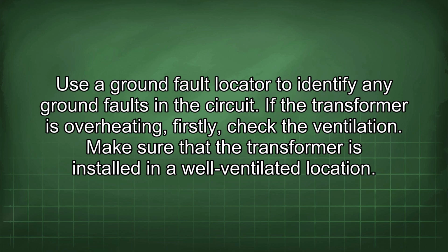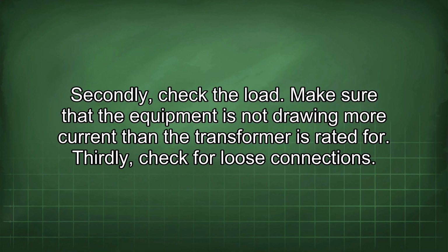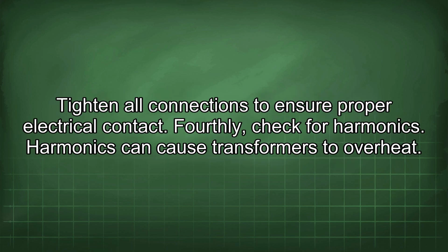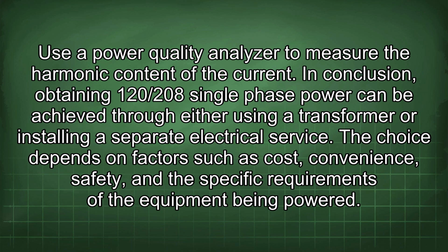If the transformer is overheating, firstly, check the ventilation. Make sure that the transformer is installed in a well-ventilated location. Secondly, check the load. Make sure that the equipment is not drawing more current than the transformer is rated for. Thirdly, check for loose connections. Tighten all connections to ensure proper electrical contact. Fourthly, check for harmonics. Harmonics can cause transformers to overheat. Use a power quality analyzer to measure the harmonic content of the current.